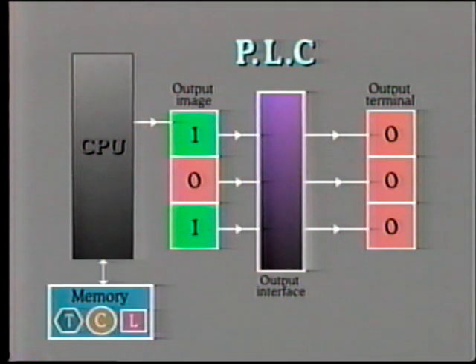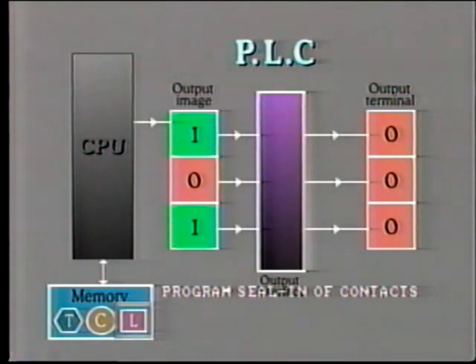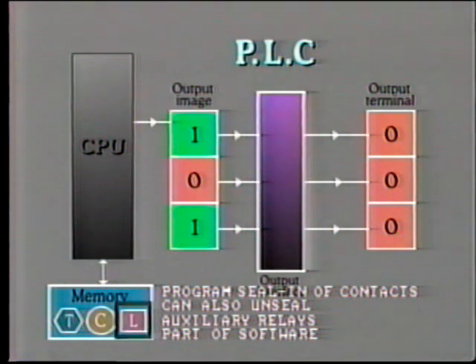Another useful function which is contained in the PLC is the latching and unlatching function. This allows us to program into the logic the seal-in of certain contacts. We can also unseal, that is, unlatch the contact when conditions demand this. So-called auxiliary relays are used for these functions, but of course these are not really separate devices. The software is written so that the particular step of the process acts like a relay.